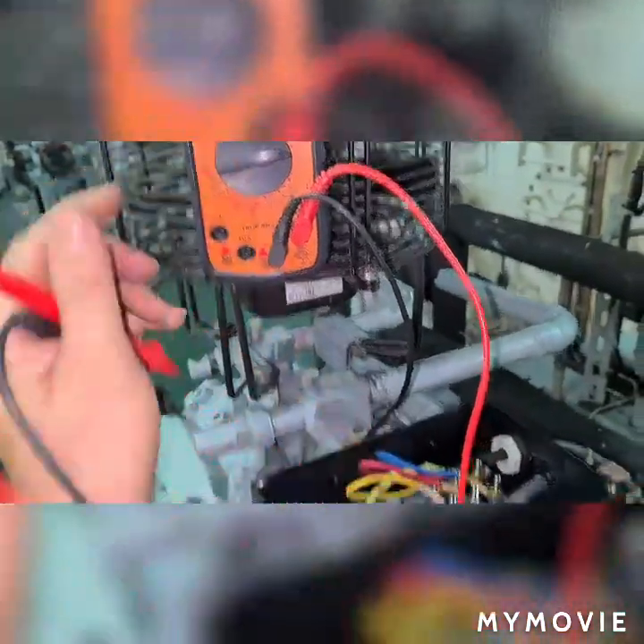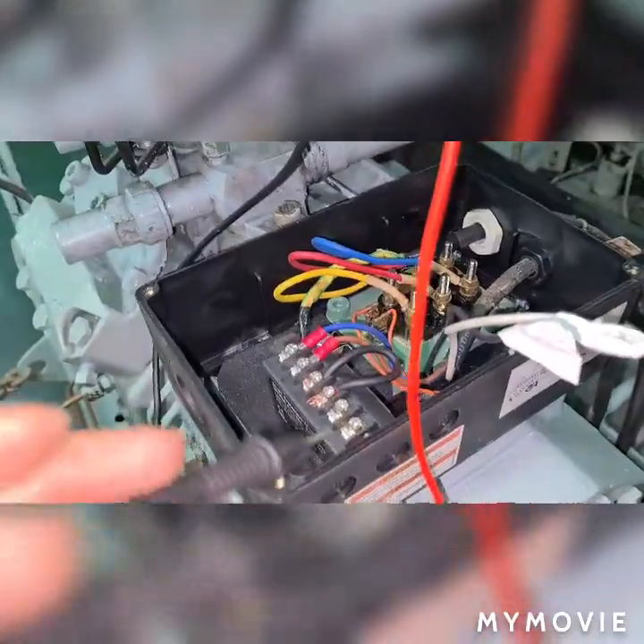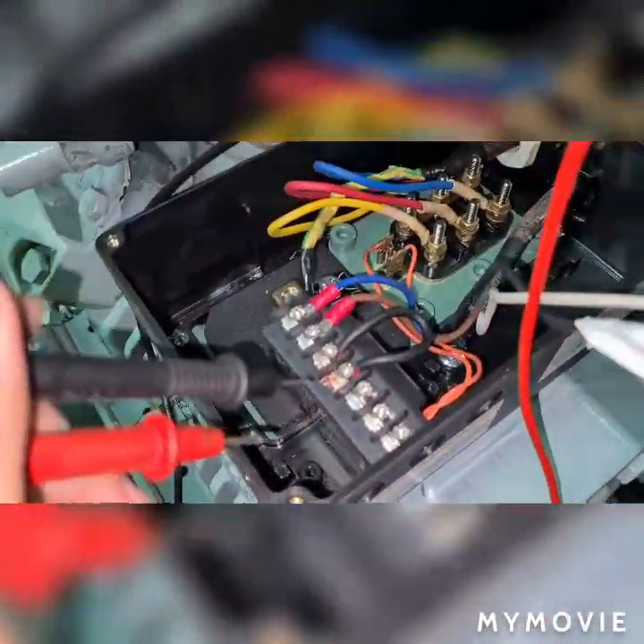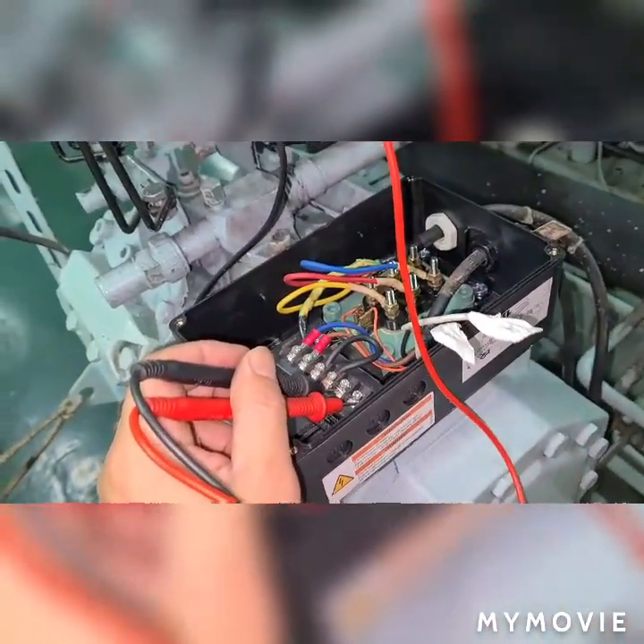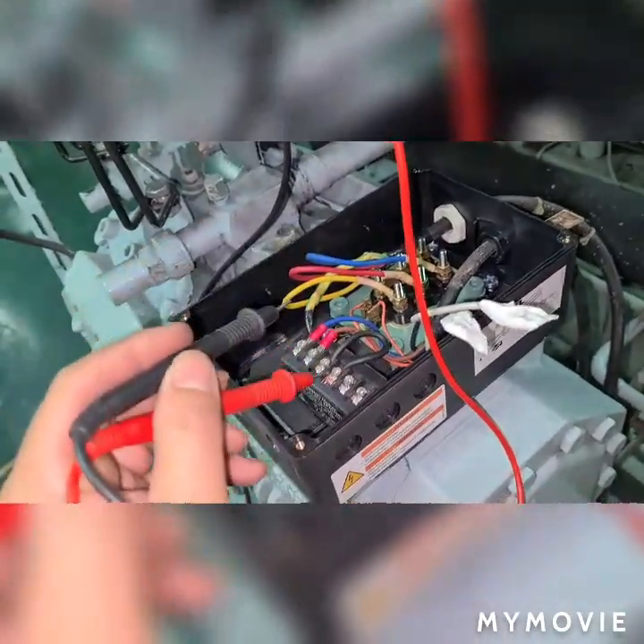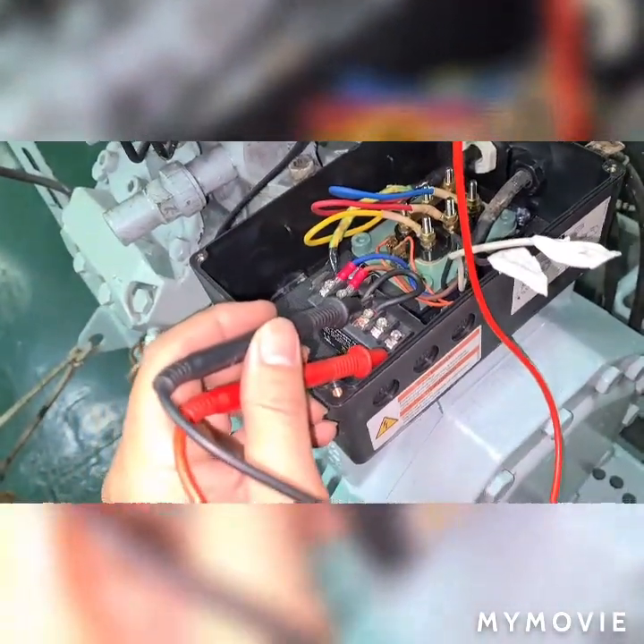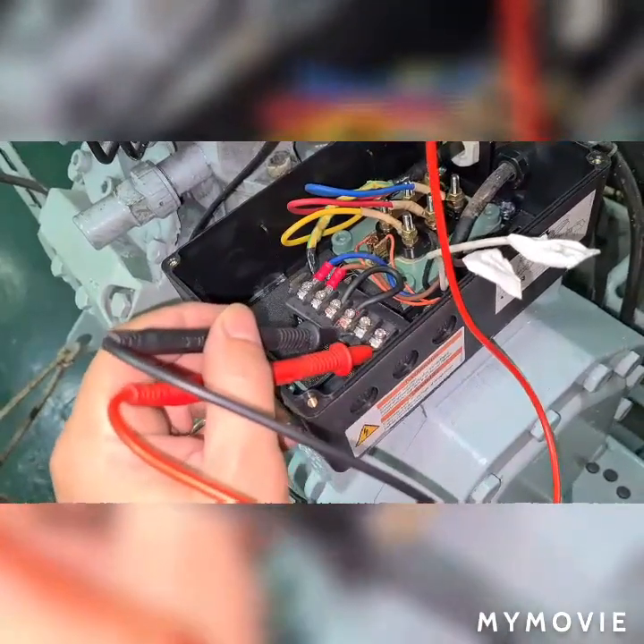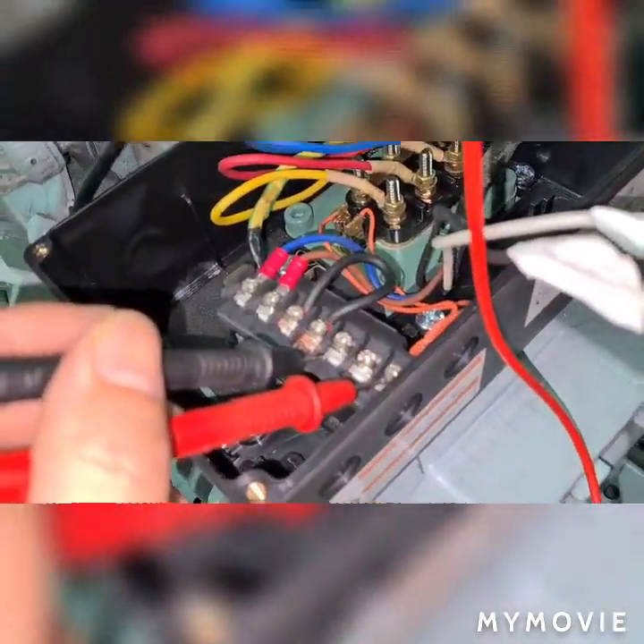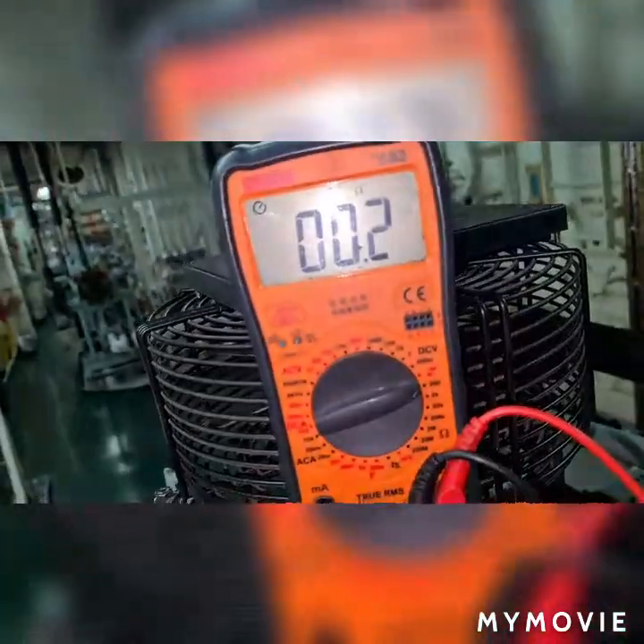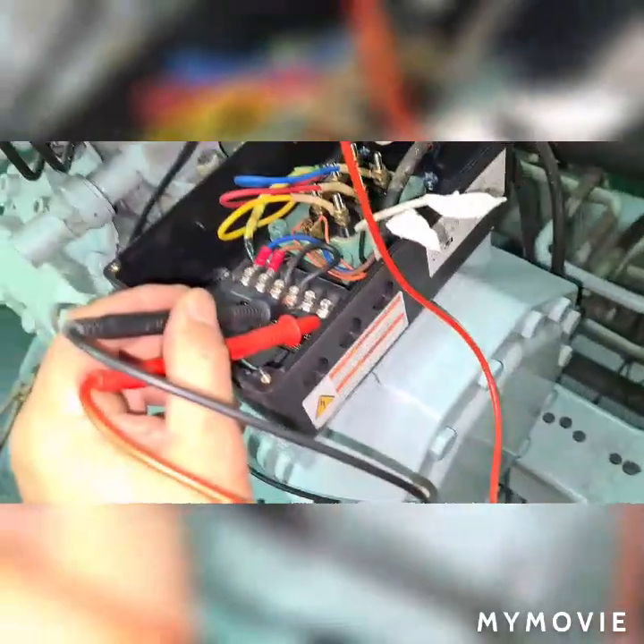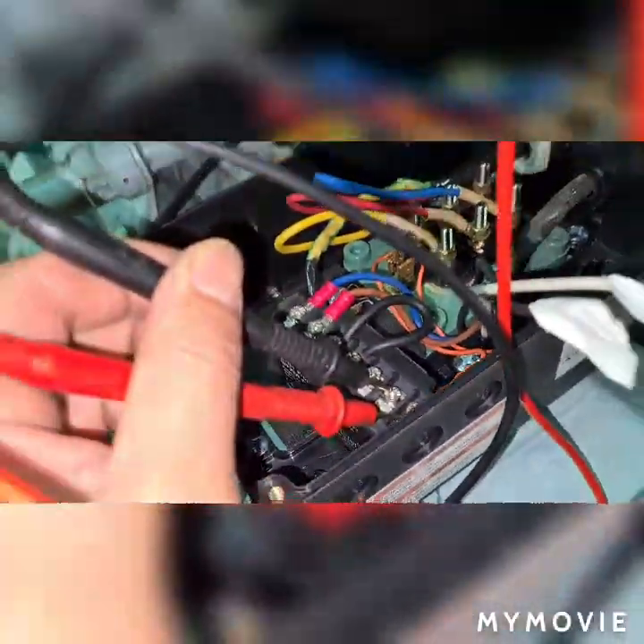Then I'm going to measure again the terminal 11 and 12, and as I verified, I just take the continuity on 11 and 12, and as you notice here, the 11 and 12 remain normally closed. See, and the terminal 11 and 14 having a normally open contact in here.